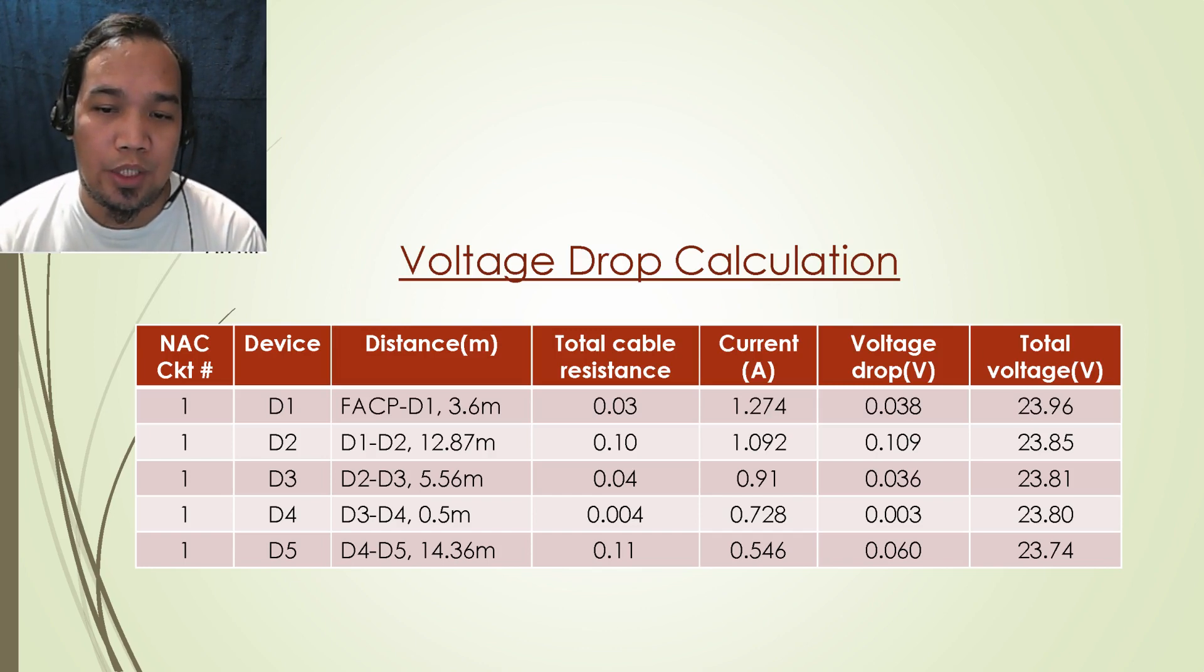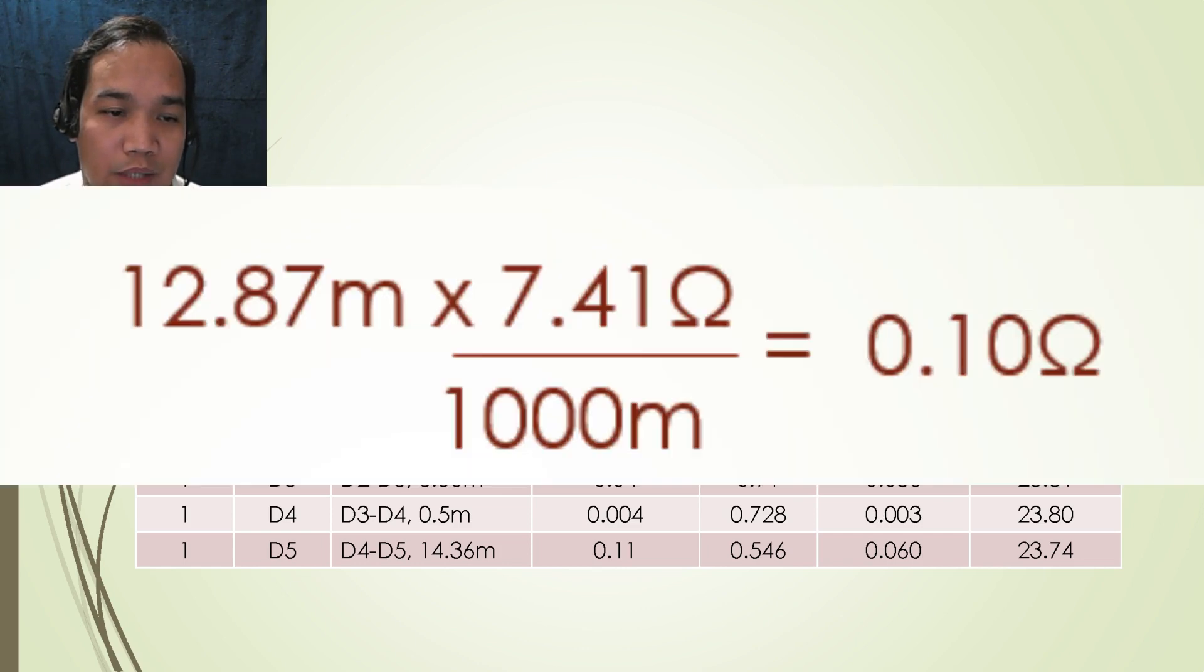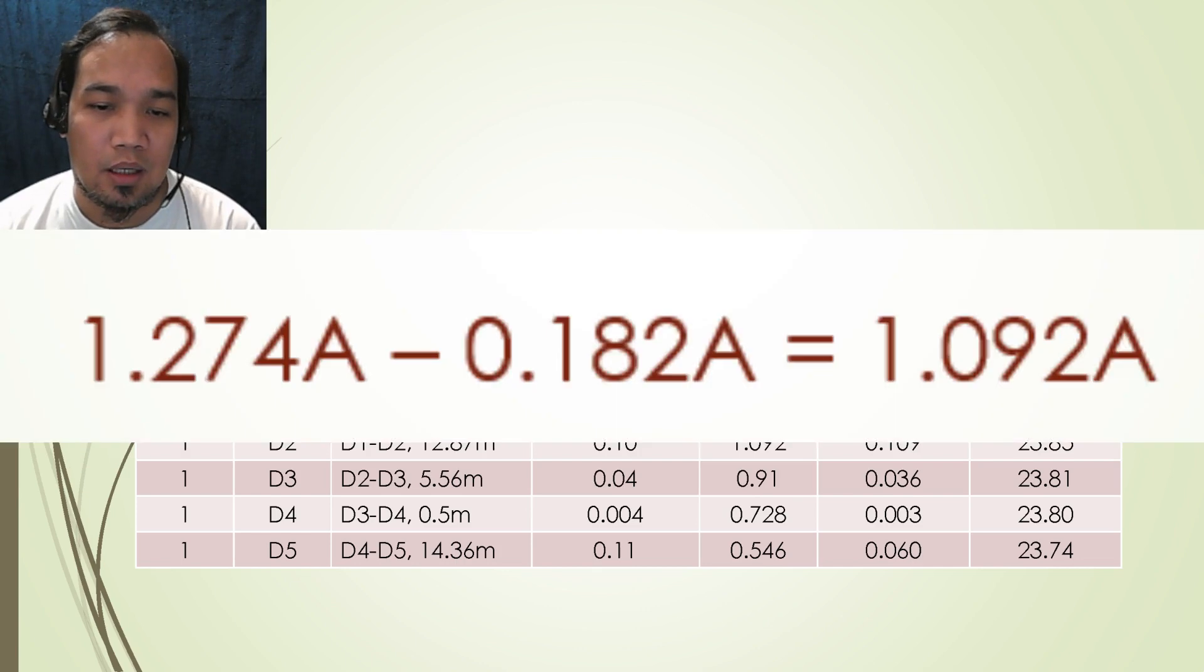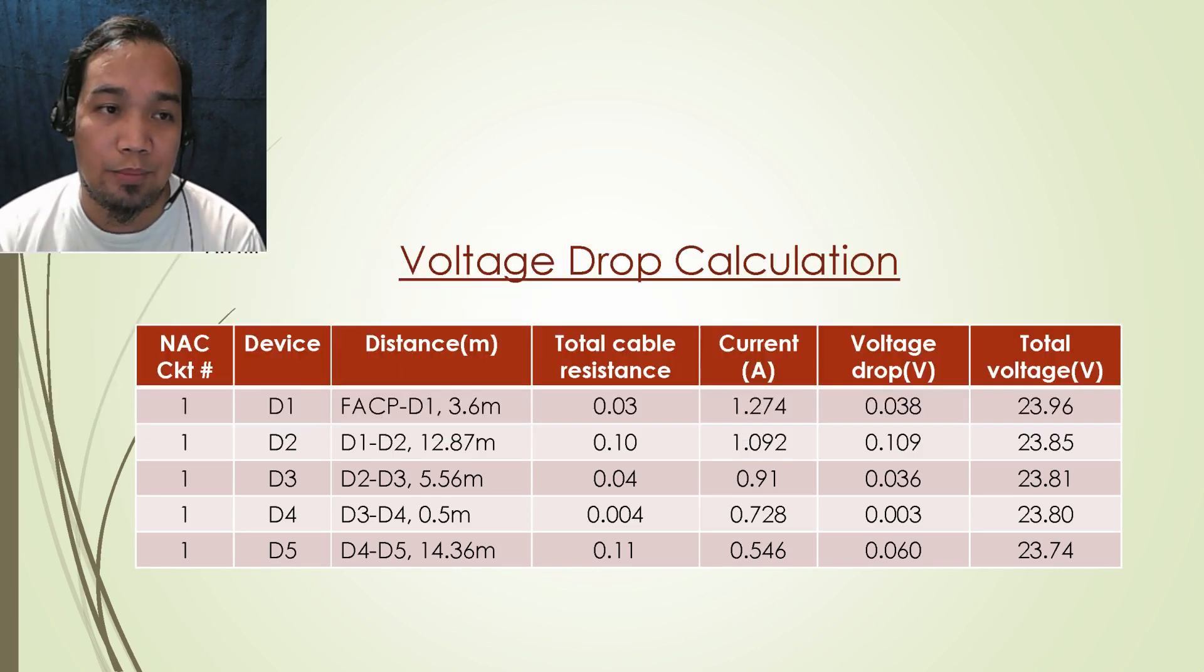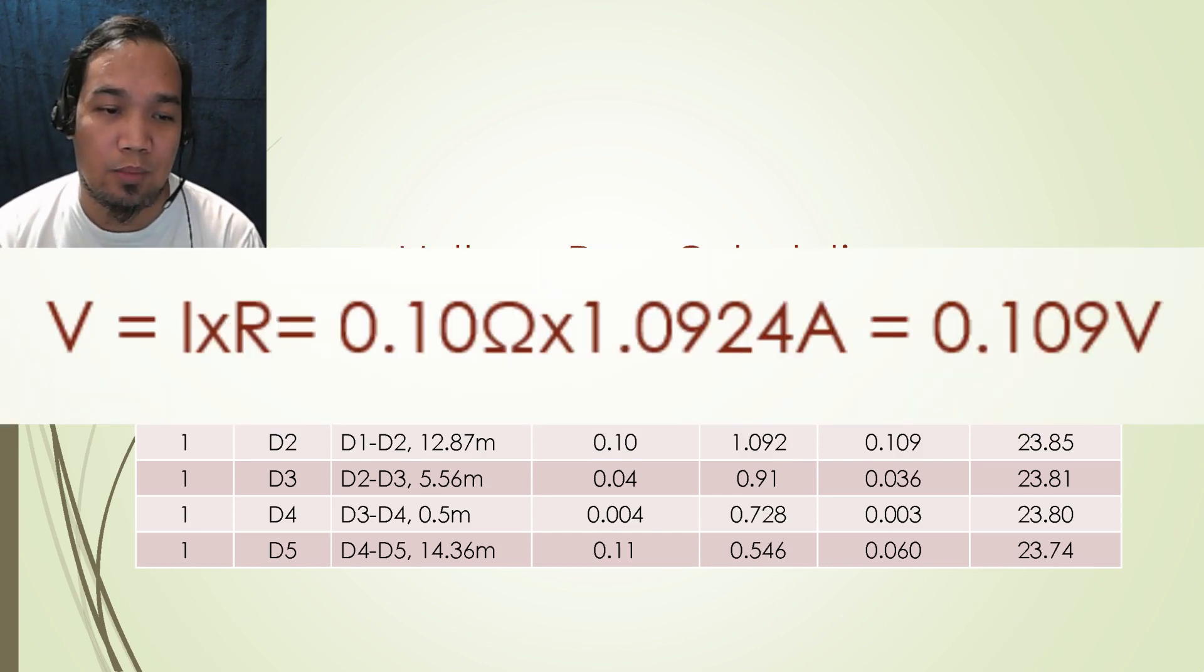For the next row which is for the second device, the distance from the first device to the second device is measured. With the same data sheet of cable, a value of 0.10 ohms is calculated. For the current, the current to be used can be calculated by deducting the current of first device from the total current, which results to a value of 1.092 ampere and 0.109 volts voltage drop using Ohm's law.